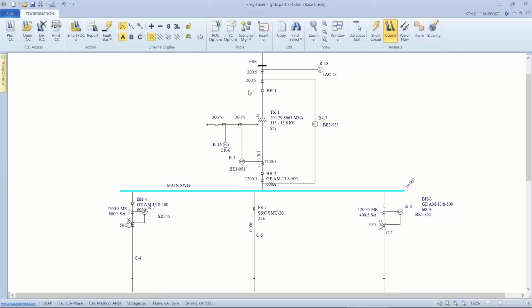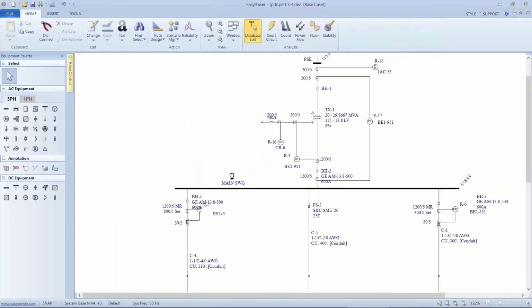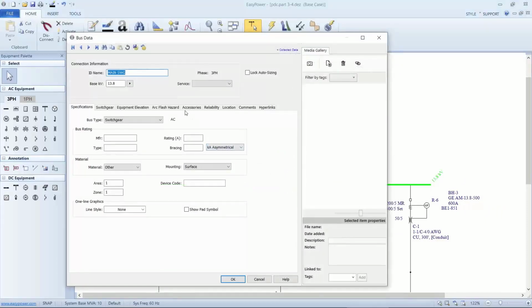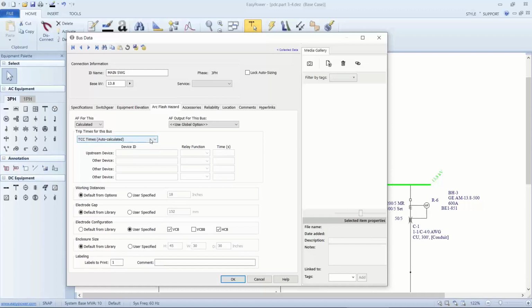So the way it's simulated as far as protection, when we go to set that bus up downstream, let's go ahead and see. When we have set this bus up for the downstream bus, under the arc flash hazard, instead of just looking at the calculated times, we say, well, we also want to look at the user-defined times. And this would be, I believe, R17. The relay function would be 87, or the differential. And the time element includes the relay response time according to the data sheet, and then the opening time for whichever breaker the relay is tied to. And that summation, or that total, will give us the total response time that the manufacturer's data sheet will support. So whatever that total time is, we use in this column.